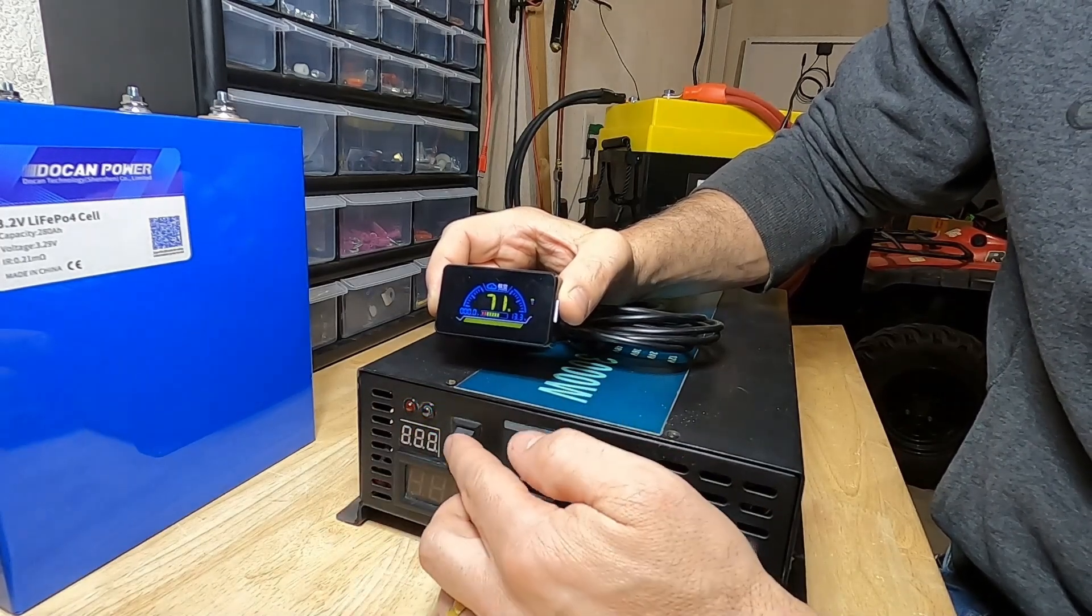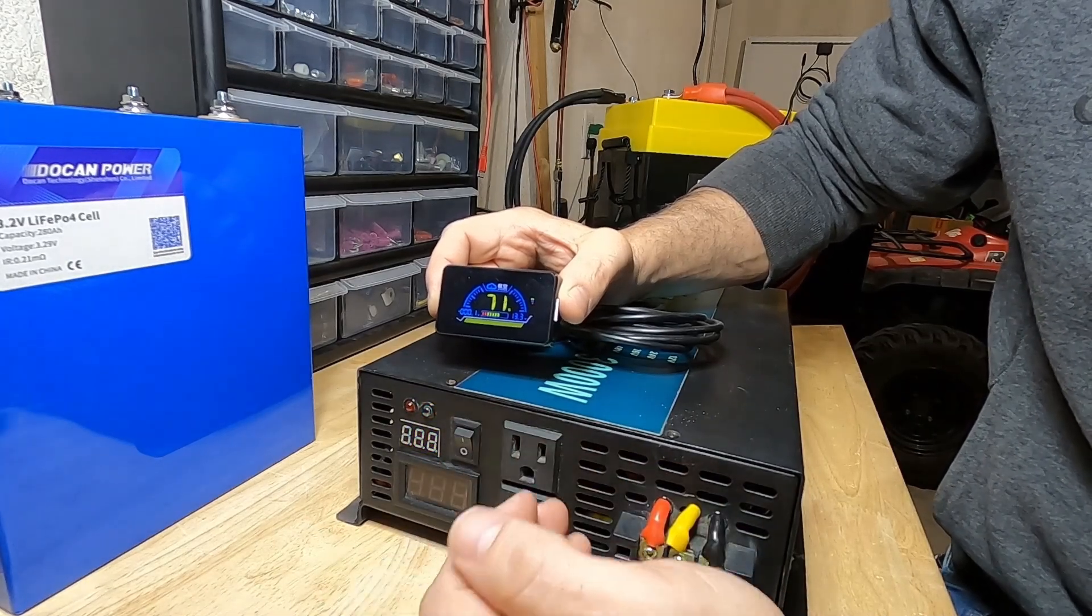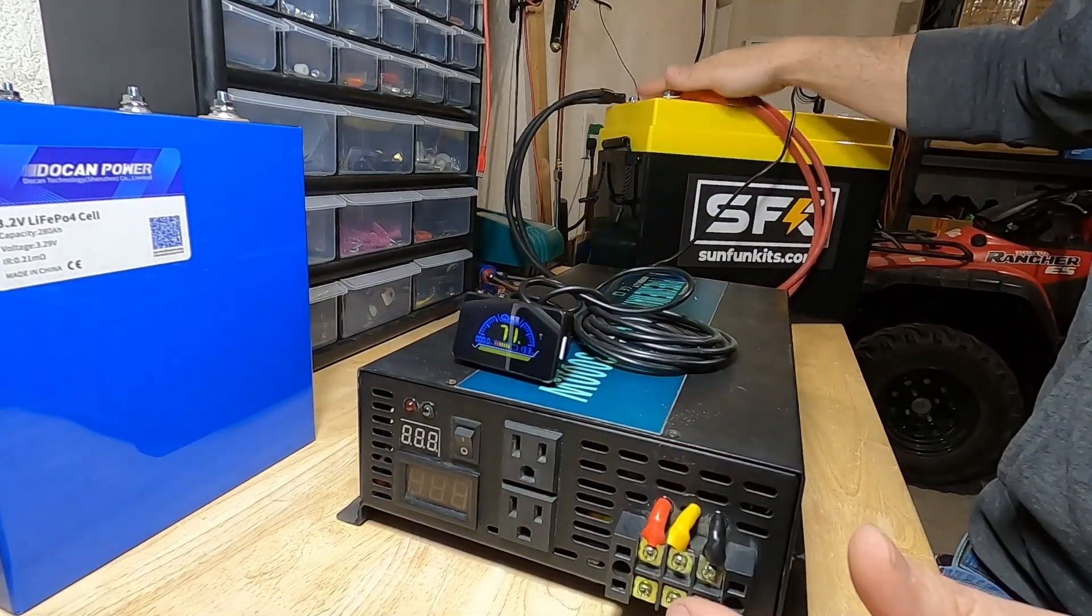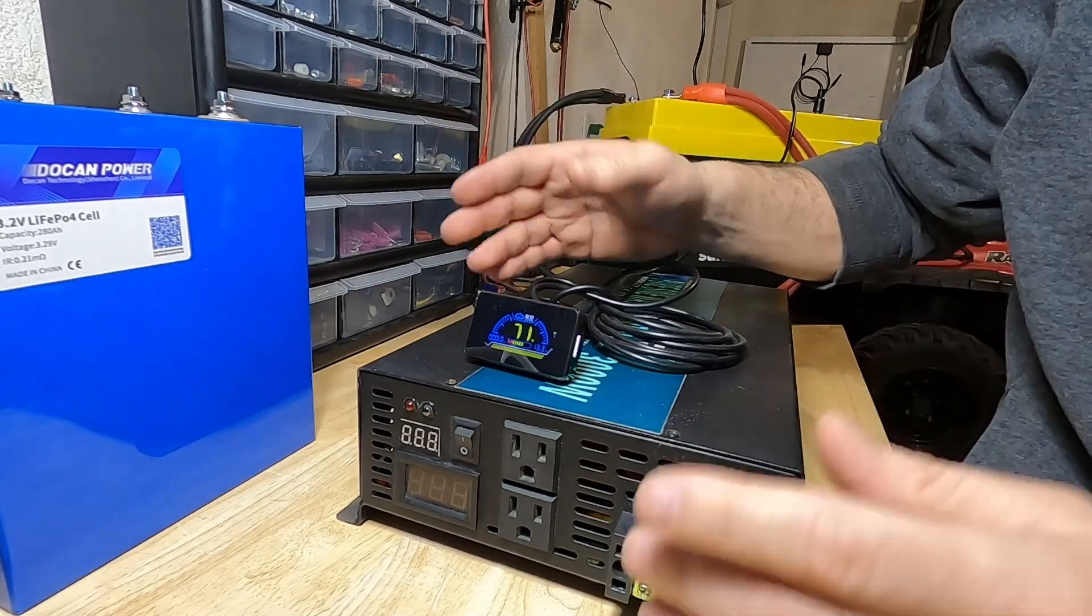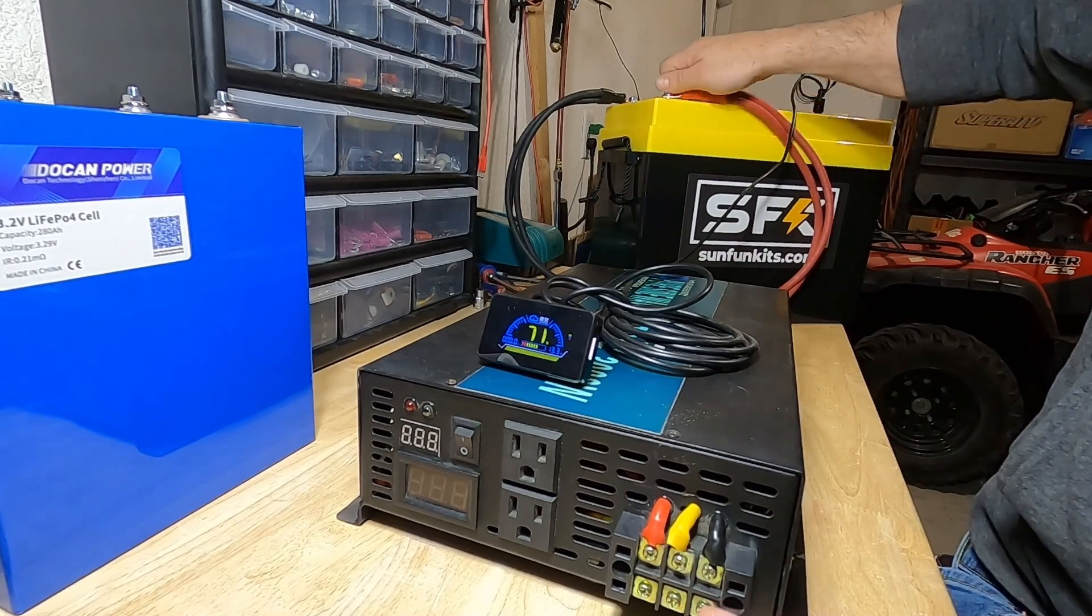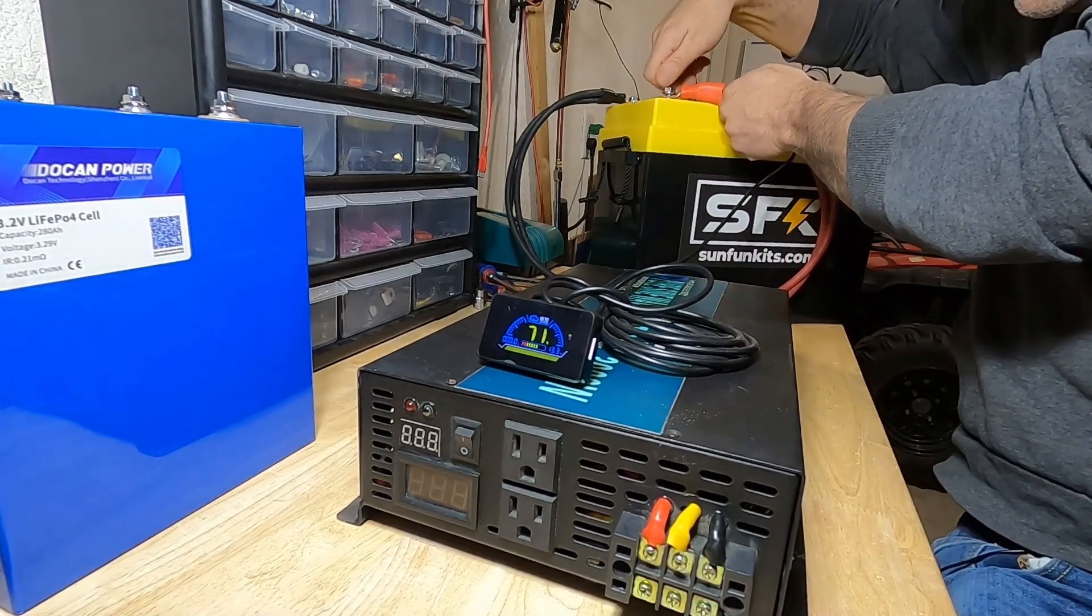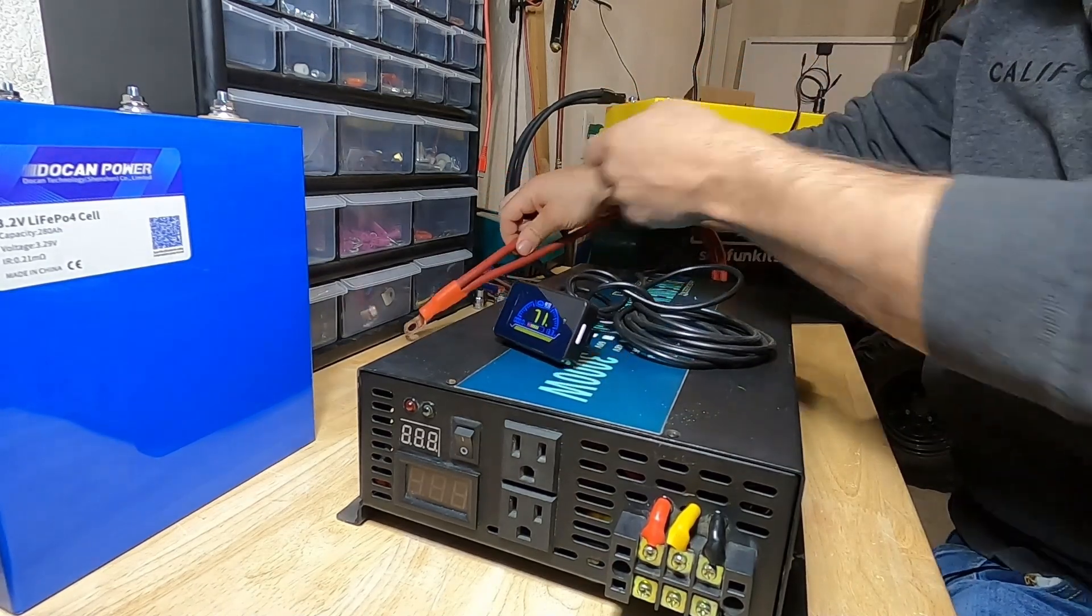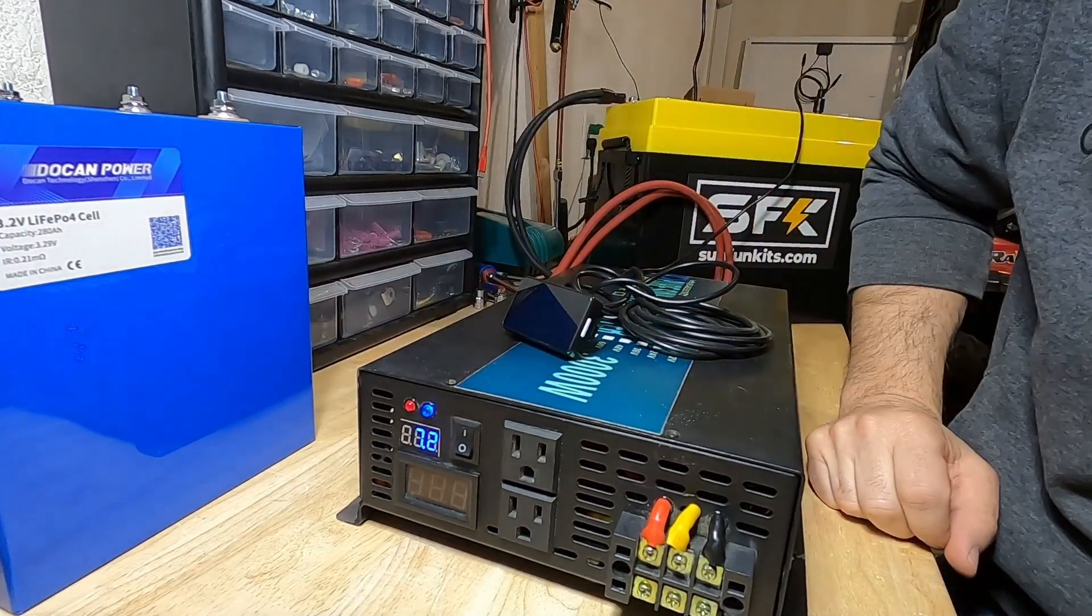Don't get those confused—don't think 'oh well I turned it off, made the sound, and it's discharged, it's all good.' You want to disconnect the battery. If you can't actually turn off your battery, like a lot of batteries you buy on Amazon, there's no display—you have to actually disconnect the cable from the battery. So I'll do that just to illustrate what you would have to do: physically disconnect, and you should always physically disconnect the battery from your inverter.